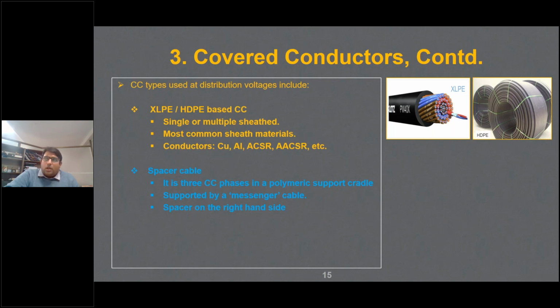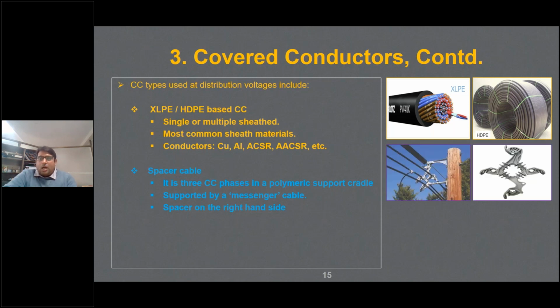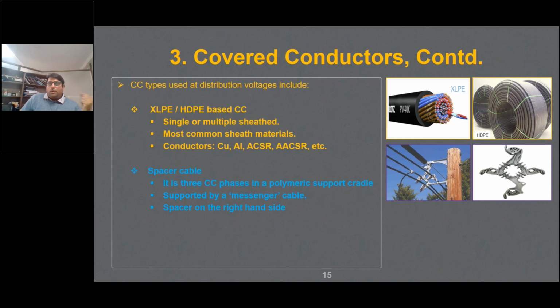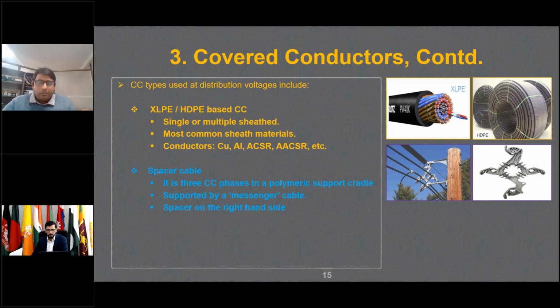You can also see that there is a single sheath, mostly, for that matter. Now we come to the second part, that is the spacer cable. Kindly refer to your right-hand side again. The spacer cable is a three-phase covered conductor in a polymeric spacer cradle. You can see the cradle over here as well, and it is supported by a messenger cable, and the spacer is on the right-hand side. The spacer causes a typical space between this triangular arrangement of conductors. So they keep them at a distance, and they also provide mechanical strength, as they are subjected to winds and other kinds of calamity that may occur in the field.